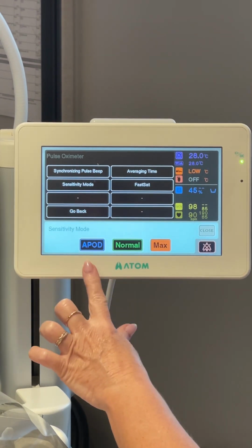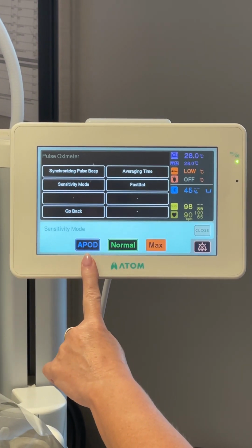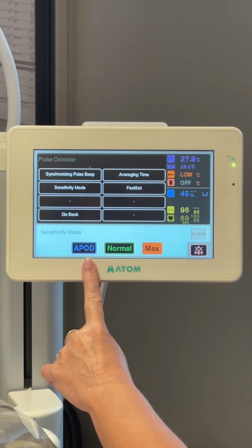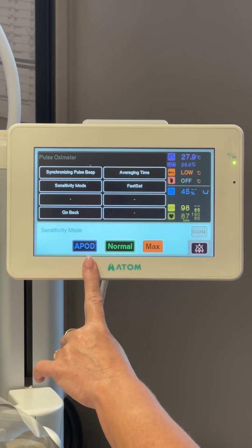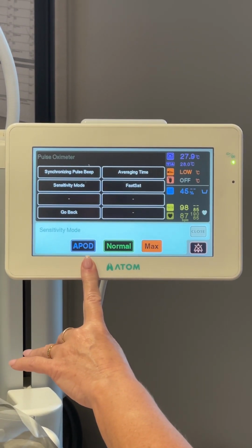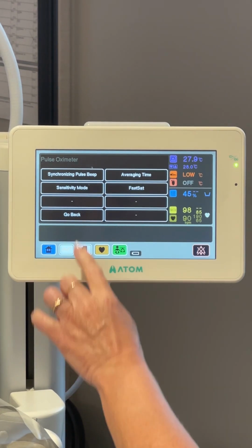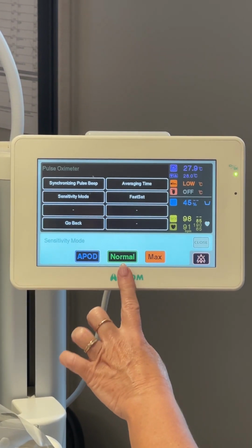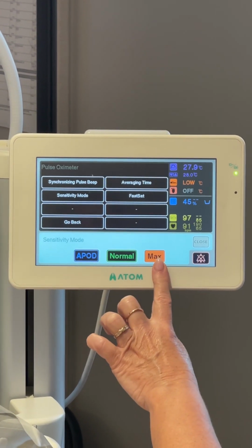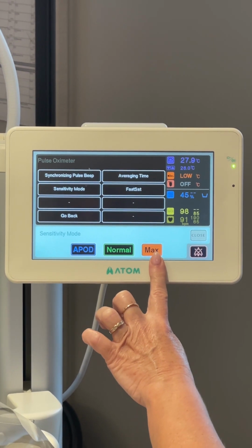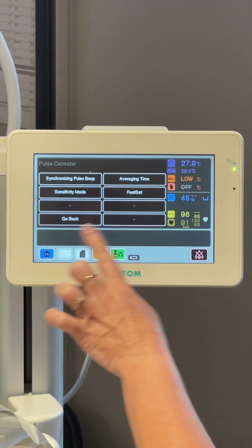We can change the sensitivity mode. APOD stands for Advanced Probe Off Detection. I think that's more for ward use for extremely low birth weight babies. That would not be used very frequently. But you would normally pick either normal, or if you have a poorly perfused baby and are having trouble getting a pulse ox reading, choose max.